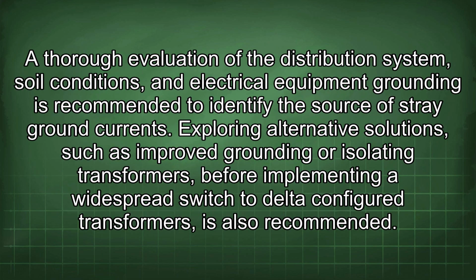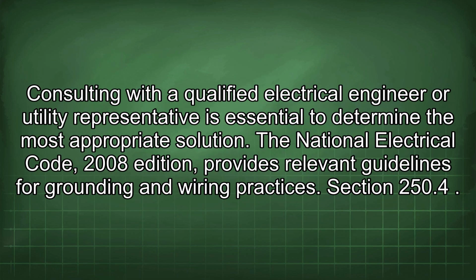A thorough evaluation of the distribution system, soil conditions, and electrical equipment grounding is recommended to identify the source of stray ground currents. Exploring alternative solutions, such as improved grounding or isolating transformers, before implementing a widespread switch to delta-configured transformers is also recommended. Consulting with a qualified electrical engineer or utility representative is essential to determine the most appropriate solution. The National Electrical Code, 2008 edition, provides relevant guidelines for grounding and wiring practices.